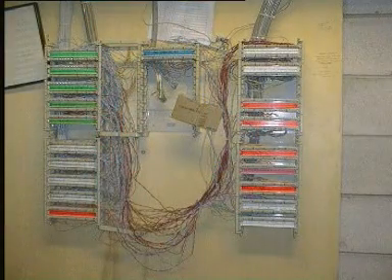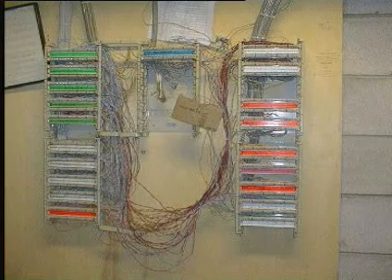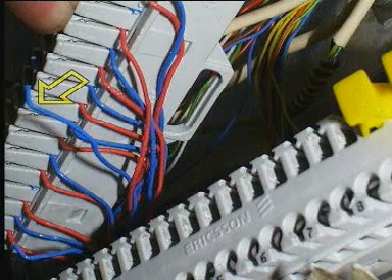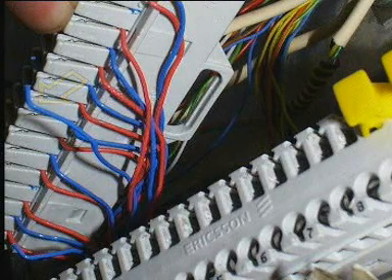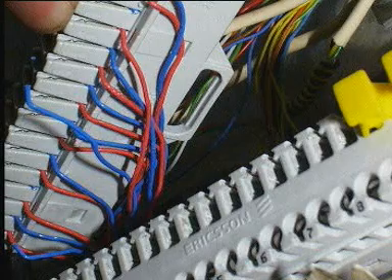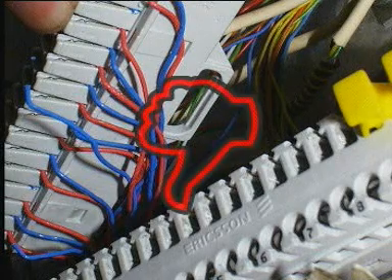This distribution frame for cross-connection was actually brought into service. It looks untidy and has no cable markings. This badly connected cable could have been due to improper use or the use of a defective tool, if one was ever used. This installation is unacceptable.